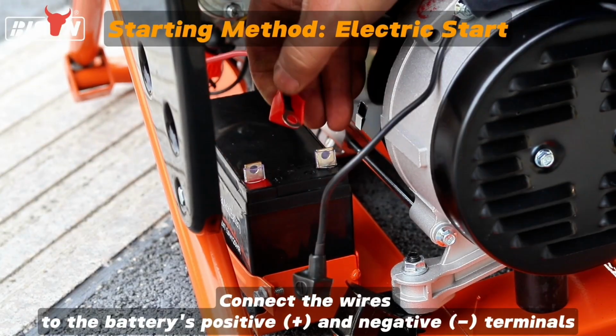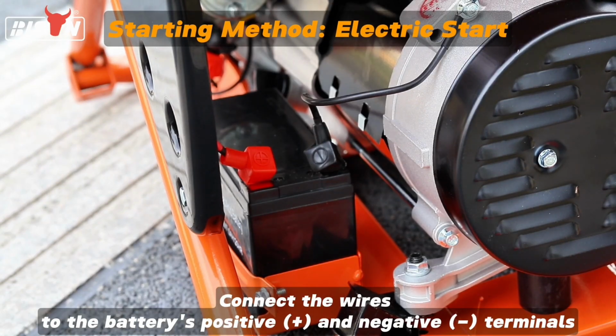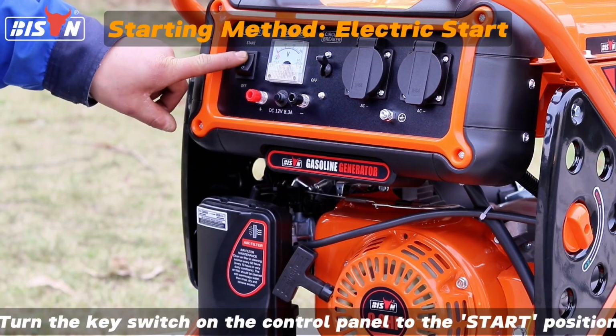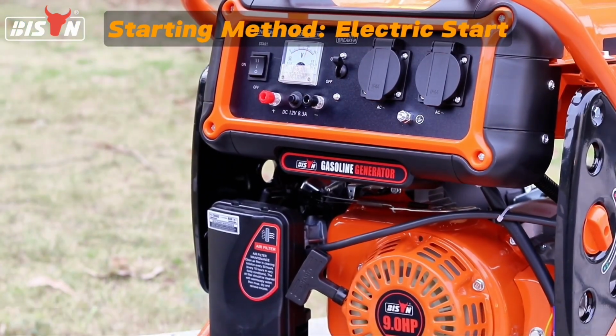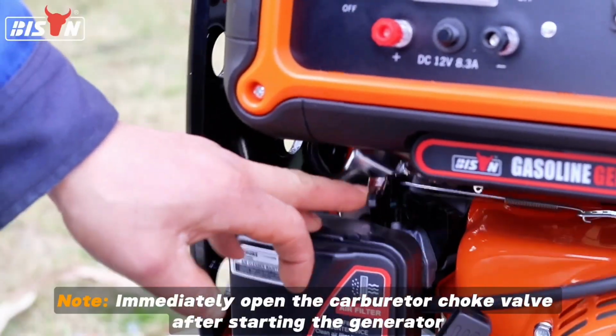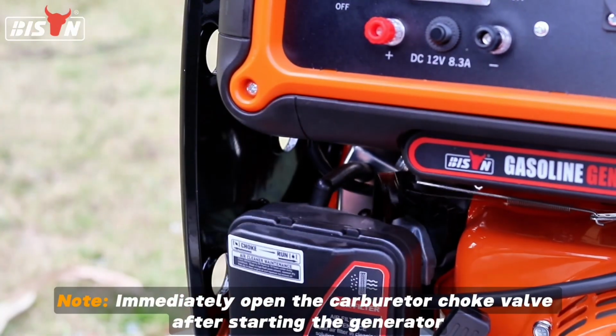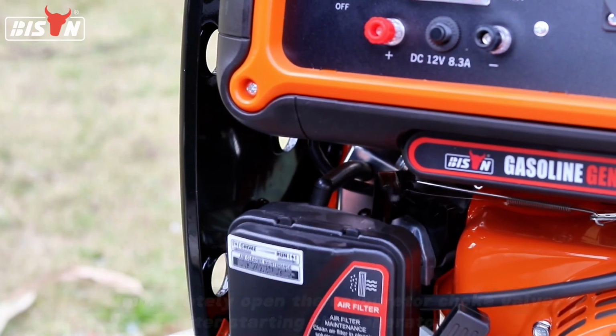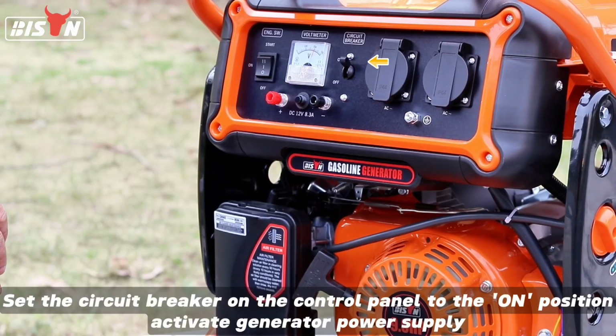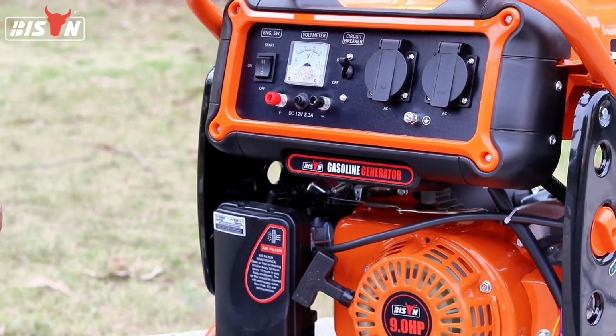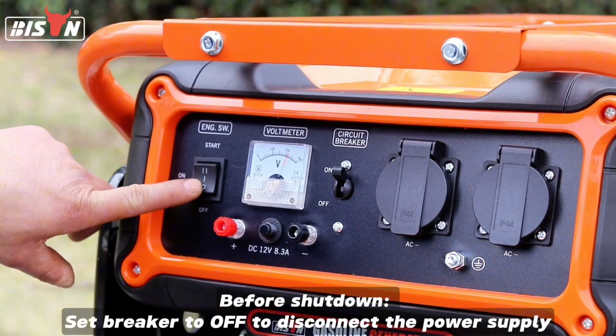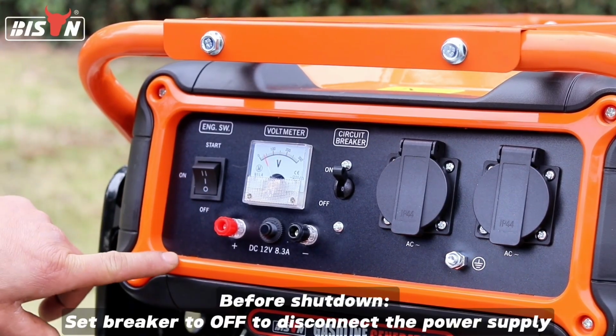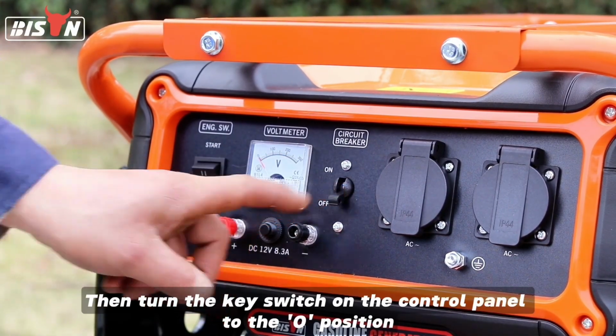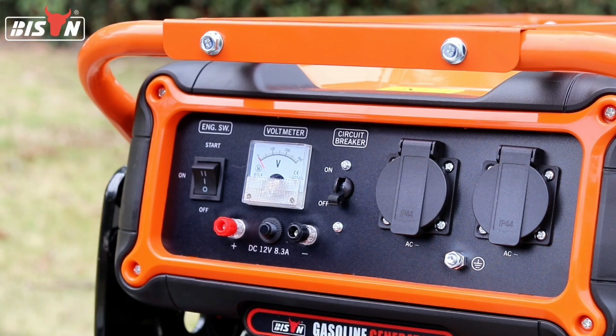Connect the wires to the battery's positive plus and negative terminals. Turn the key switch on the control panel to the start position. Note: immediately open the carburetor choke valve. After starting the generator, set the circuit breaker on the control panel to the on position. Activate generator power supply. Before shutdown, set the breaker to OFF to disconnect the power supply. Then turn the key switch on the control panel to the O position.